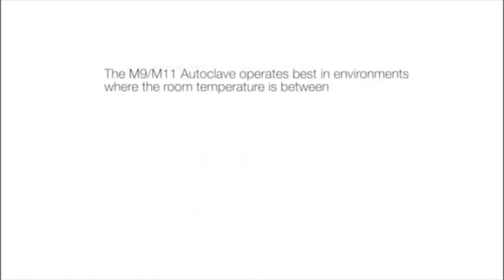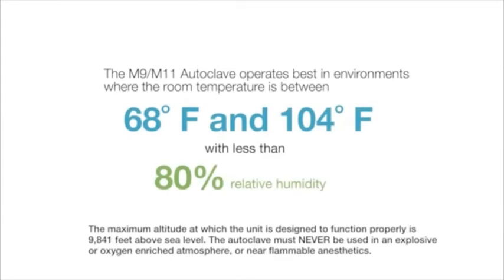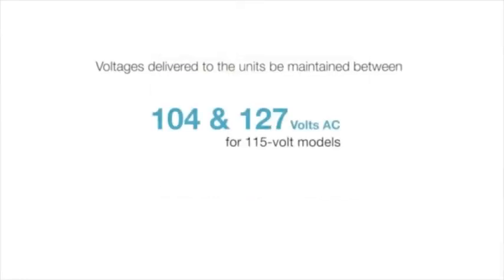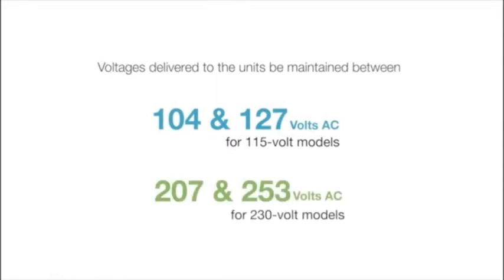The M9 M11 autoclave operates best in environments where the room temperature is between 68 degrees Fahrenheit and 104 degrees Fahrenheit with less than 80% relative humidity. M9 and M11 autoclaves are available in either 115-volt or 230-volt AC configurations. It is critical that the voltages delivered to the units be maintained between 104 and 127 volts AC for 115-volt models and between 207 and 253 volts AC for 230-volt models.